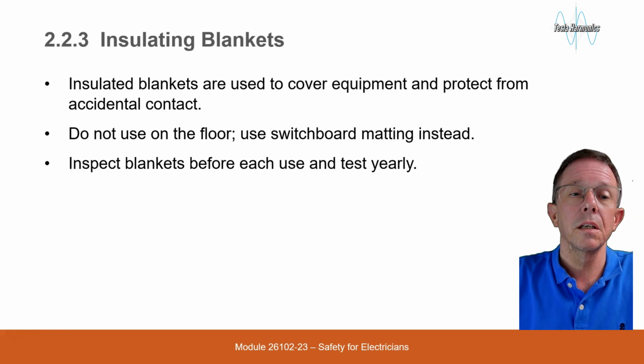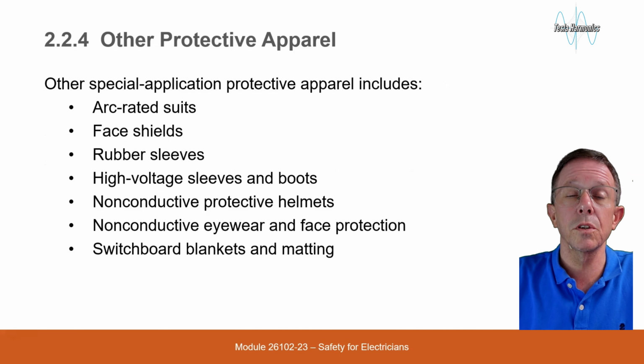Insulating blankets. Insulating blankets are used to cover equipment and protect from accidental contact. Do not use on the floor. Use a switchboard matting instead. Inspect blankets before each use and test yearly.